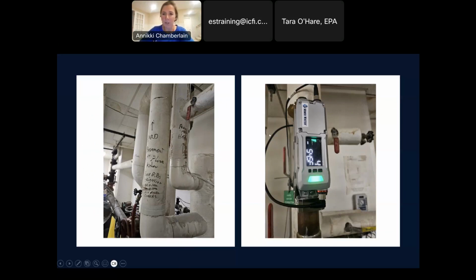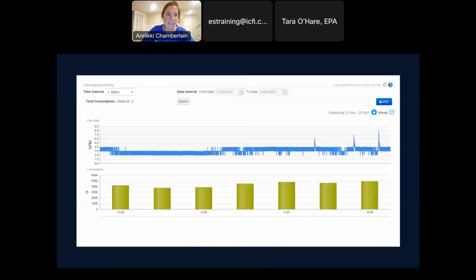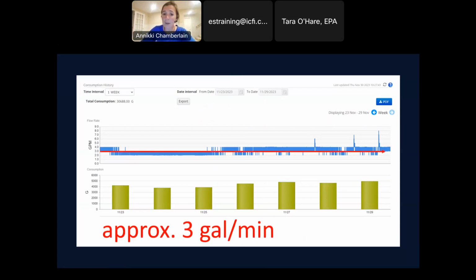So we were able to do quick diagnostics, clamp on the meter. It's reporting through a cellular connection. So I can put it on, and I don't have to go back to the facility. And voila, we see that we found approximately 3 gallons a minute constant flow. This is over a period of a week. But it's just constant, so that's 3 gallons a minute.